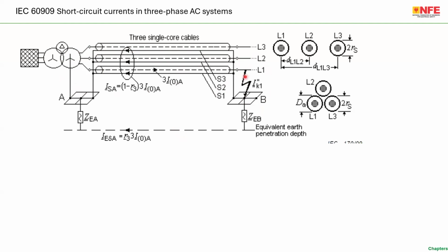IK is the peak short circuit fault current. A portion of the fault current will flow through the shield, which is connected from station B to station A. This is station B, this is station A. Through the shield wire, the majority of the fault current is flowing. A portion of the fault current is also flowing through ZE, the impedance of the earth electrode in station B. So basically, a portion of the total fault current goes through the metallic fault return path and a portion through the earth electrode of both the stations.